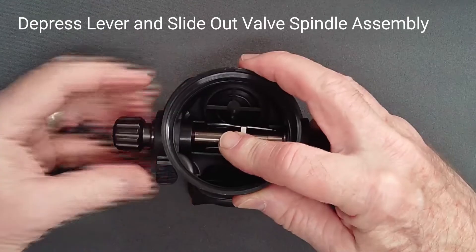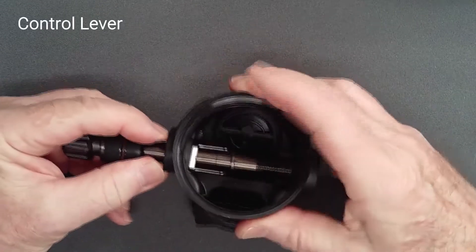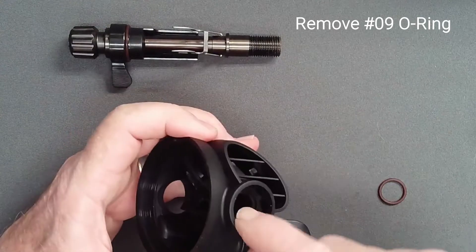Depress the lever and, grasping the control lever, slide the valve spindle assembly out of the case. Keep control of the lever. If it has not already fallen free, remove the case o-ring from its groove.